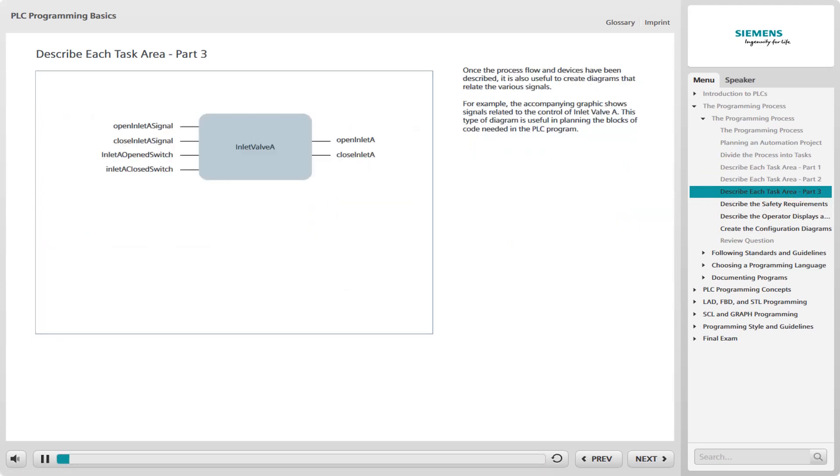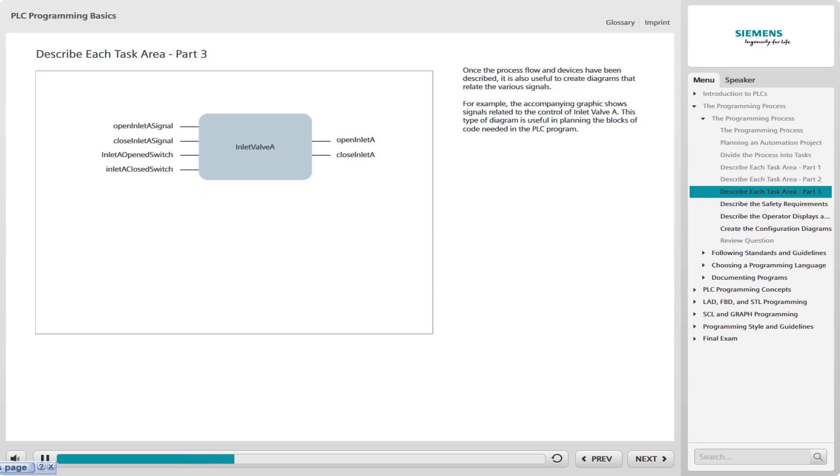Once the process flow and devices have been described, it is also useful to create diagrams that relate the various signals. For example, the accompanying graphic shows signals related to the control of inlet valve A. This type of diagram is useful in planning the blocks of code needed in the PLC program.